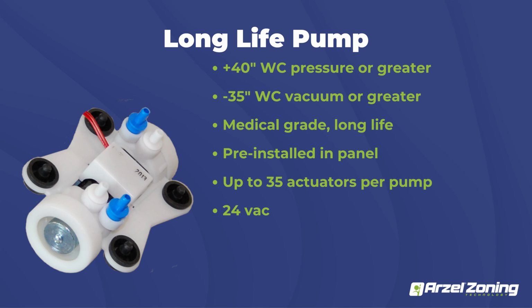Like I mentioned earlier, we are a pneumatically driven system. So pre-installed in every single one of our panels is going to be our pump. It looks just like the picture here. It was originally designed to be a kidney dialysis pump, so it has a really long life expectancy. It doesn't fail very often, and it actually creates a pressure and a vacuum simultaneously. So when you're looking at the top of the pump, there are 4 ports up there. The 2 back ones are the only ones that are actually used. The 2 front ones are always going to be vent ports, so we're either pulling in air or dispelling the air from those ports. And when you look at your pump, your back left side is your positive pressure, and the back right side is your vacuum pressure. And that's how we actually operate the dampers themselves.